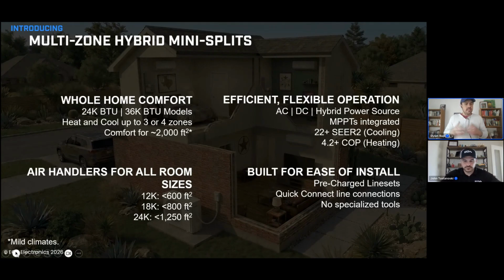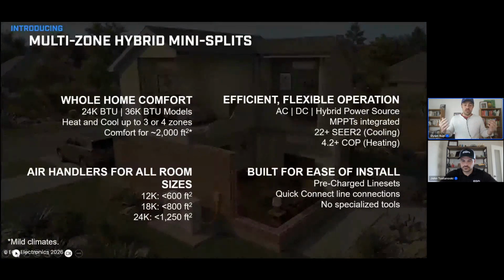And then, I didn't mention it on our single zone units, but it's worth mentioning for both of these classes of models, these are really built to enable easy installation. These come with pre-charged line sets and quick connections, which enable you to go ahead and install these units with no specialized tools or specialized equipment. You won't have to pull a vacuum. You won't have to charge the unit with refrigerant, which does require specialized tools and competencies.